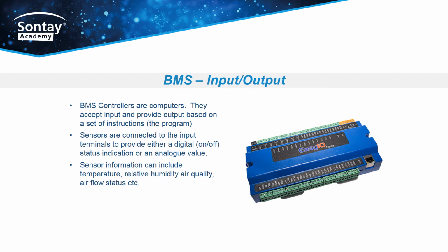When we talk about sensors, we are generally referring to analog sensing devices, whereas digital devices are most commonly referred to as switches or stats. For example, a temperature sensor refers to a device where any value can be read within the sensing range, whereas a thermostat switches either on or off as temperature passes through the set point threshold.